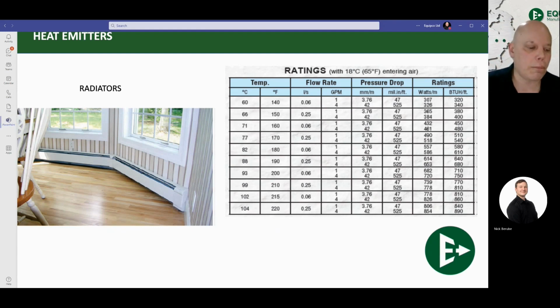So remember that first room that I did. We had that one wall that had a 480 BTU heat loss. Let's play with that. I'm going to use the coolest water I can on my chart, which is this one here. The chart starts at 140. I know that at 4 GPM, which I like because it's nice and easy, we have 340 BTUs per foot. The room itself had a heat loss of 480, so I'm going to need 2 feet of baseboard to get where I need to go. It's a little oversized, but that's fine. At least we're not undersizing it.